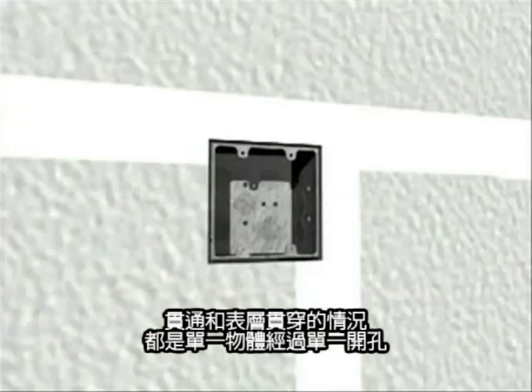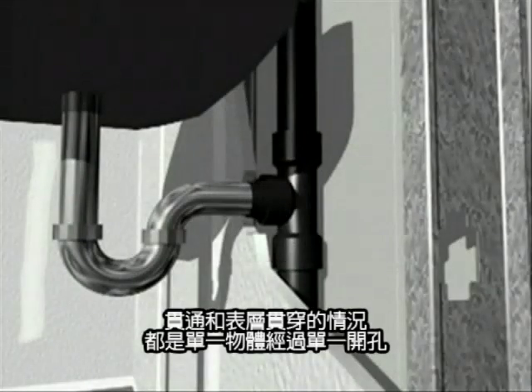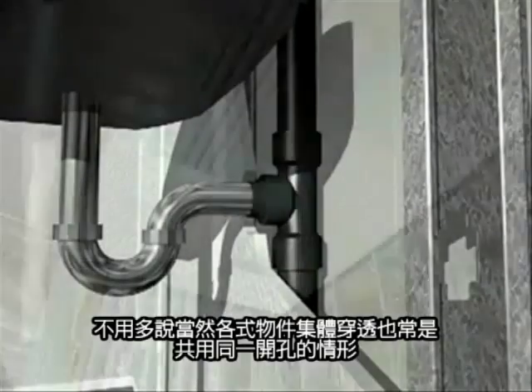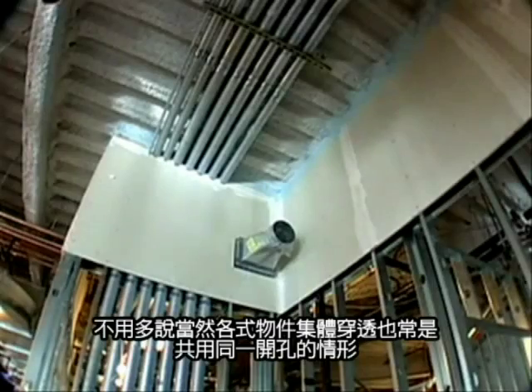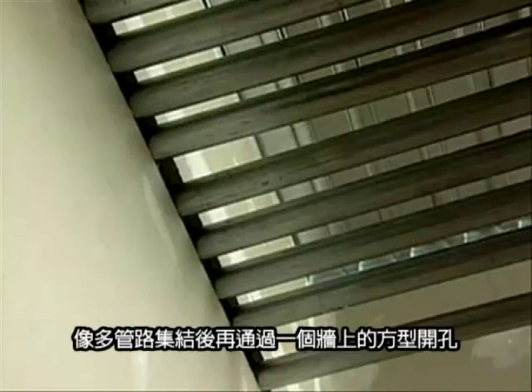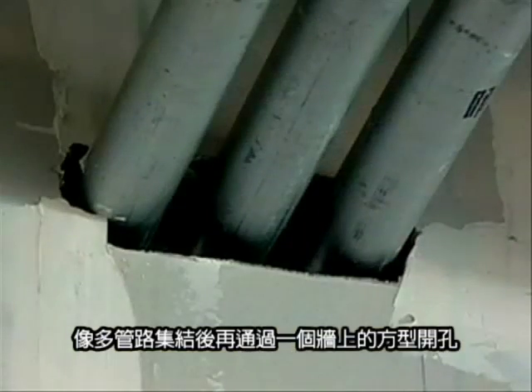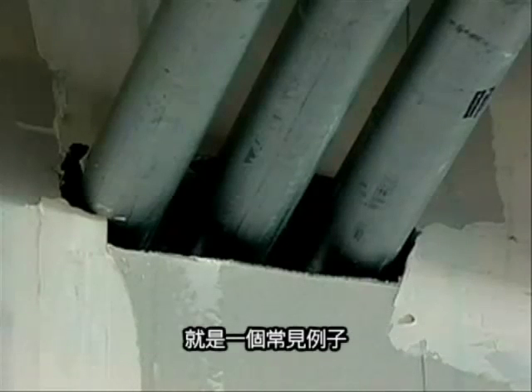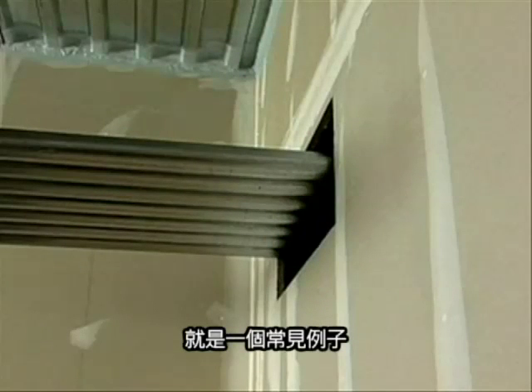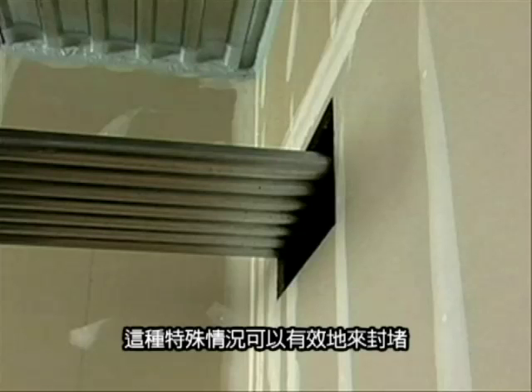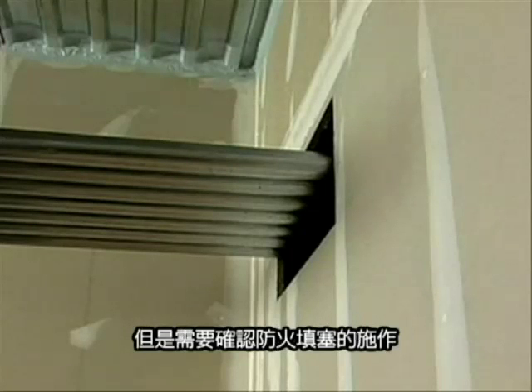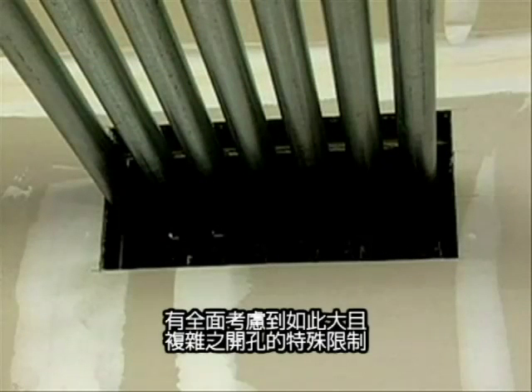Both through and membrane penetrations are examples of a single item being routed through one hole. Needless to say, grouped penetrations often share a single opening. A common example of this is where multiple conduits are racked together and routed through a large rectangular opening. This special condition can be sealed effectively, but requires care to ensure that the fire stop installation can handle the additional strain of such a large and complex opening.